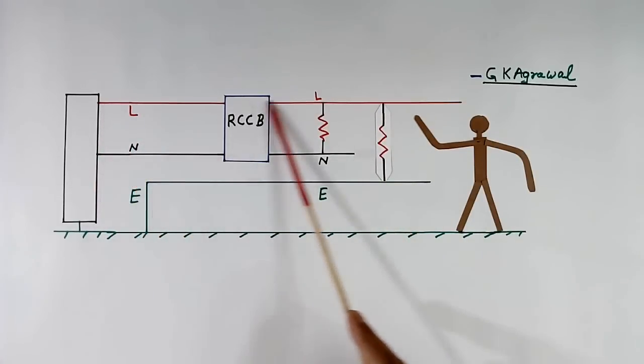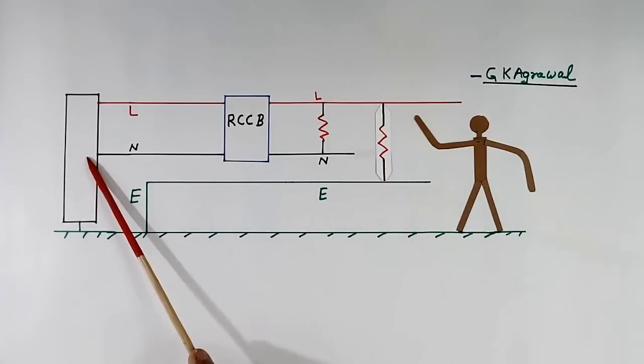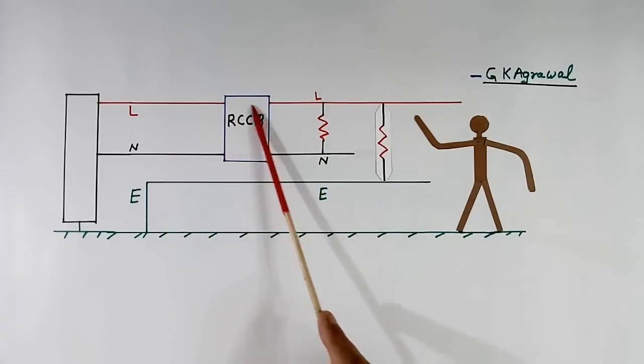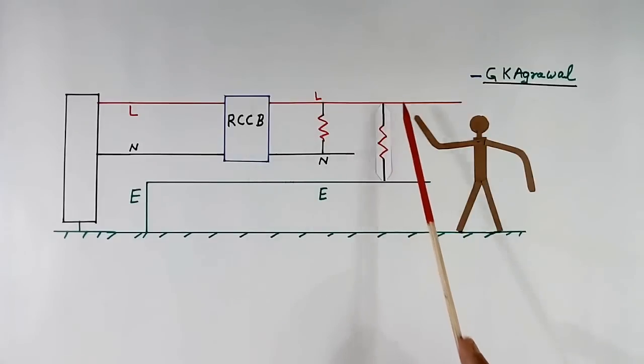Current what is going through line wire is coming back through earth wire. It is not coming back through neutral wire. So here current will flow. Here current will not flow. So this RCCB will trip, and we will not get any load.